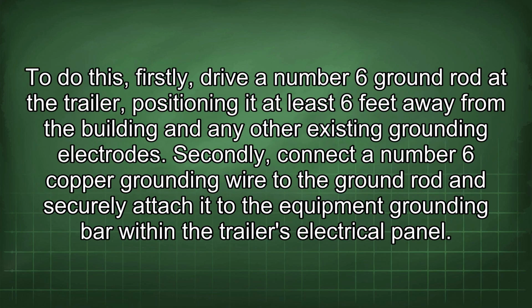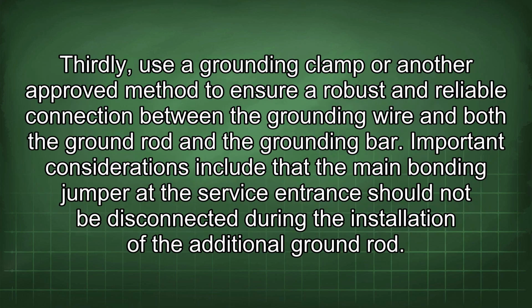250.32(D). To do this, firstly, drive a number 6 ground rod at the trailer, positioning it at least 6 feet away from the building and any other existing grounding electrodes. Secondly, connect a number 6 copper grounding wire to the ground rod and securely attach it to the equipment grounding bar within the trailer's electrical panel. Thirdly, use a grounding clamp or another approved method to ensure a robust and reliable connection between the grounding wire and both the ground rod and the grounding bar.